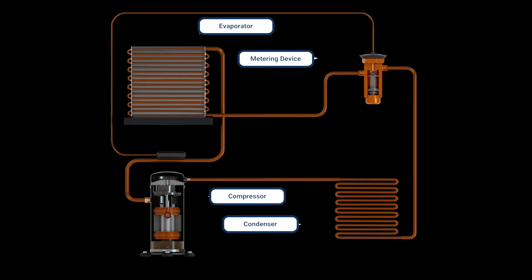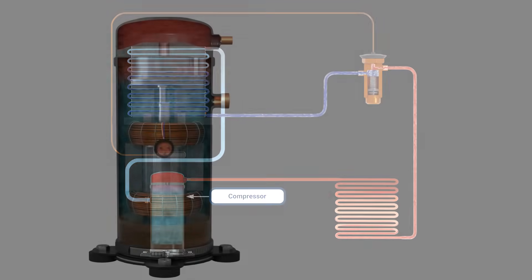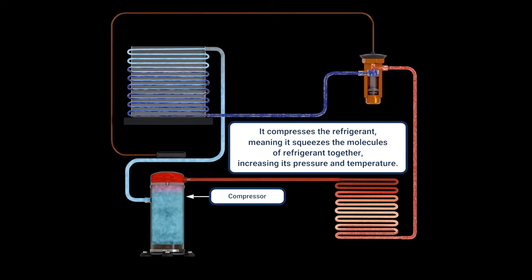Now let's look at the refrigeration cycle, starting with the compressor. It compresses the refrigerant. This means it squeezes the molecules of refrigerant together, increasing its pressure and temperature. Think of it as the heart of the system, pumping the refrigerant through the circuit, and for now, also think of it as a pressure increaser.